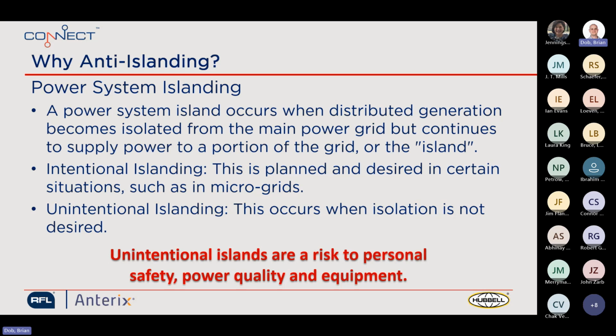And specifically, unintentional islands can be a risk to personnel safety, power quality, and also equipment damage. And so we have standards like IEEE 1547, which recommends that islands be removed within 2 seconds.